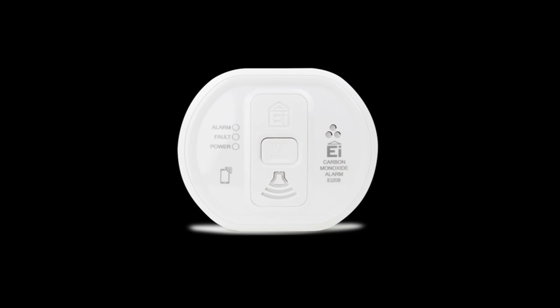So if you're not interlinking your carbon monoxide alarms, there is a chance it can rise and travel to a different room. And if that detector is only in, say, the kitchen, and you've got a long corridor, and your bedroom's at the end, and you're a deep sleeper, or you're under the influence of alcohol or drugs, or it might have been a wild night, then there might be a chance that you won't hear that standalone alarm, because it's quite important that we hear these alarms when we're asleep. So I personally believe you should interlink them. Personally, I would in my own home. But again, in some situations, you might not have to.